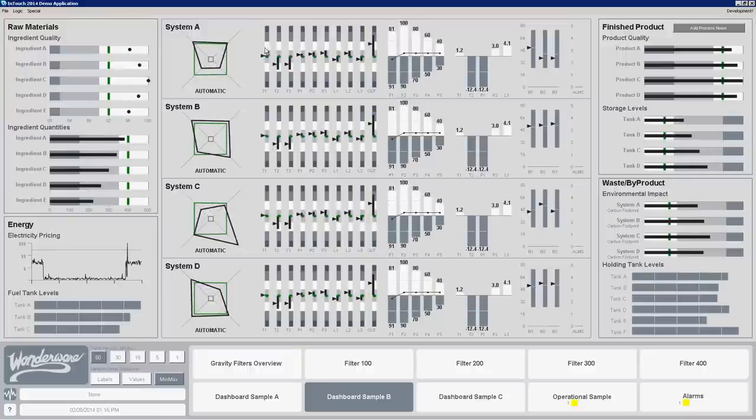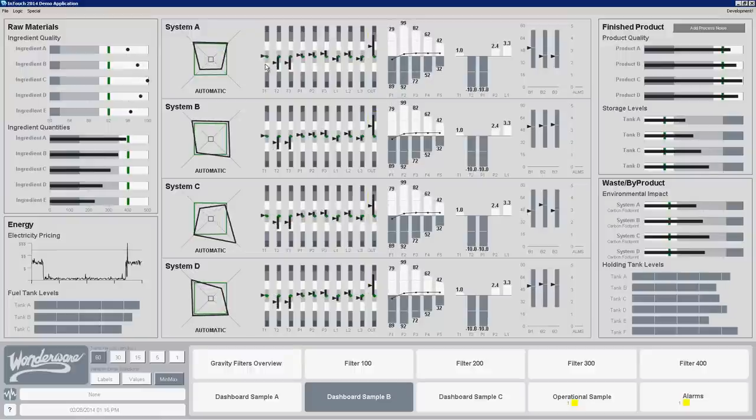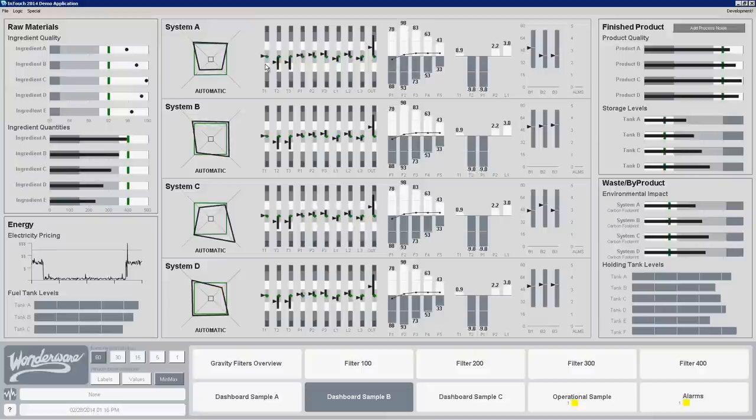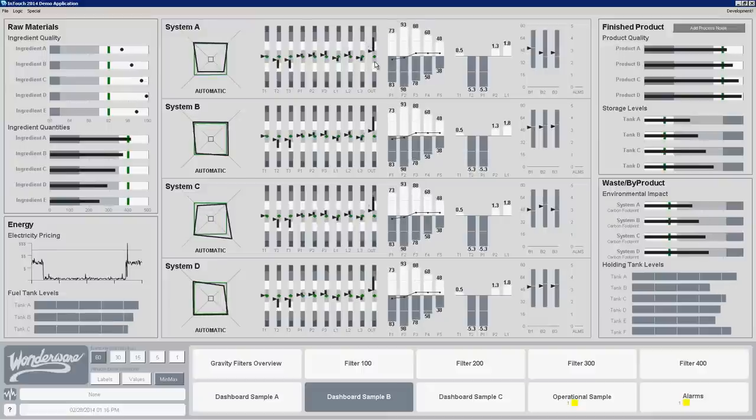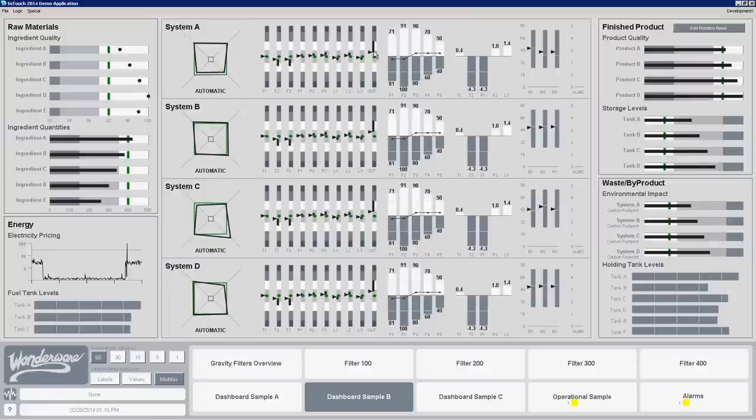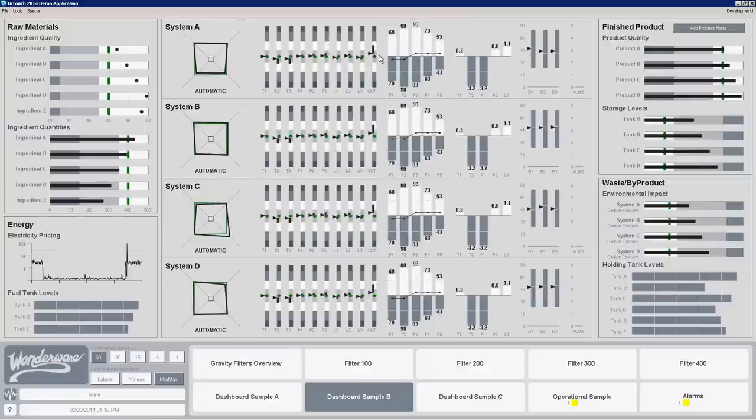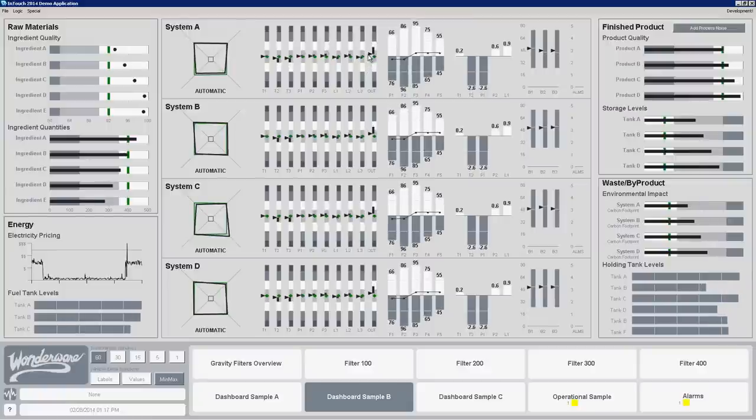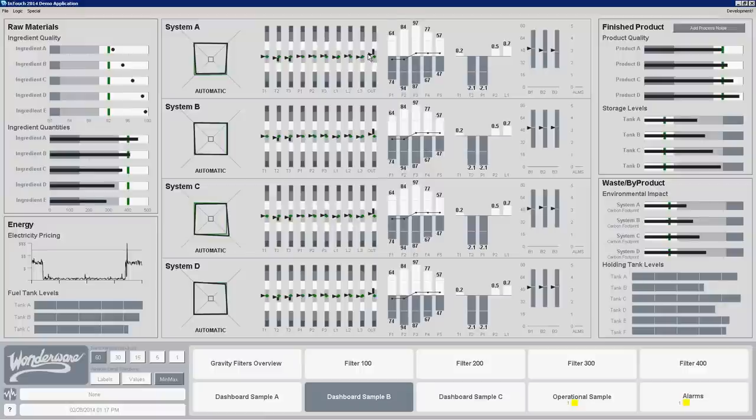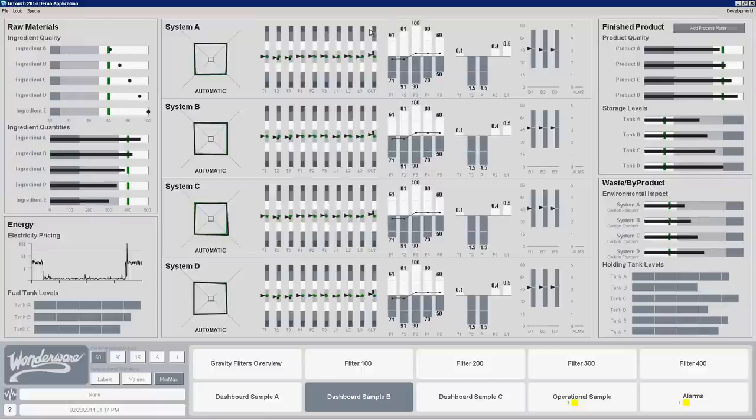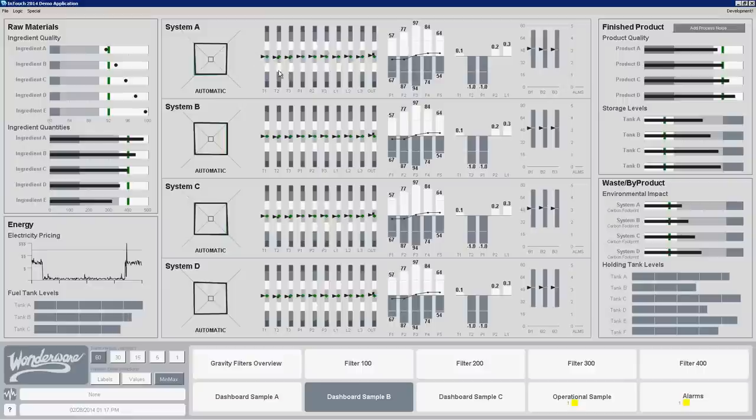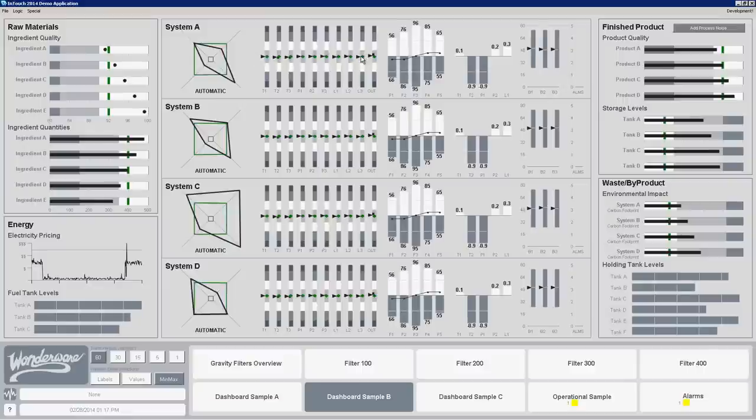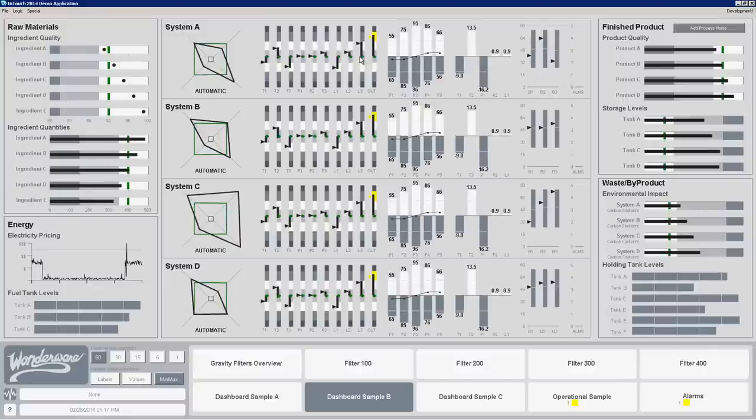So if things are outside of this gray box then I know that they're in an abnormal state. So I'm showing here this dark line on the side showing me where it's been over the past 30 seconds or so. What I can see here is my current set point, my current value, my optimal operating range, my alarm limits low and high, and my critical shutdown limits low and high. So I can quickly assess if this thing's going outside of expectation here.